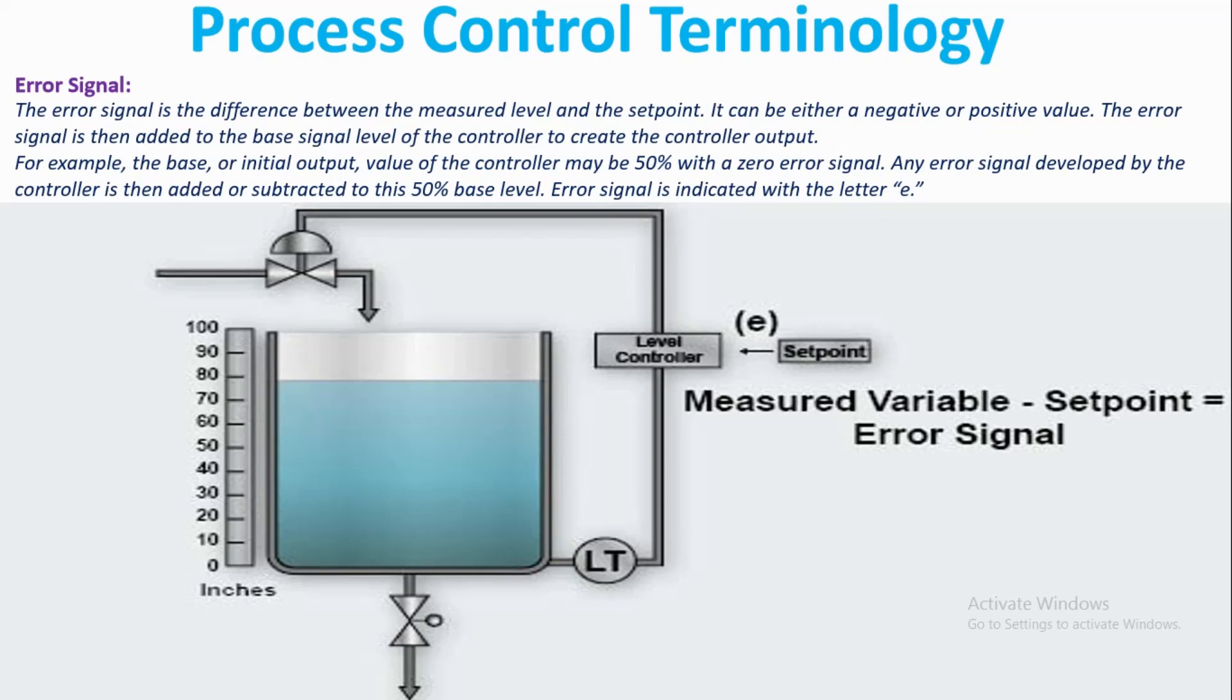For example, the base or initial output value of the controller may be 50% with a zero error signal. Any error signal developed by the controller is then added or subtracted to this 50% base level. Error signal is indicated with the letter E.